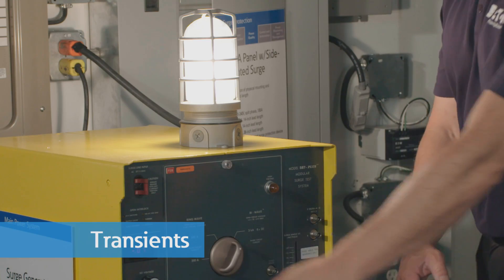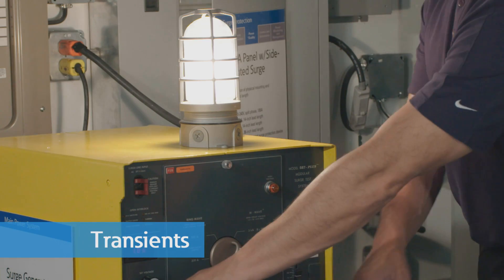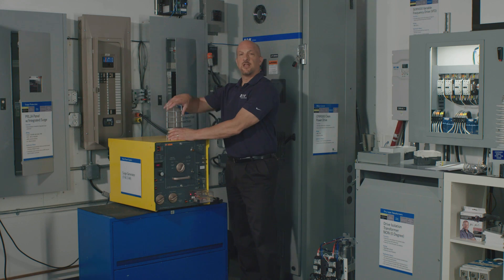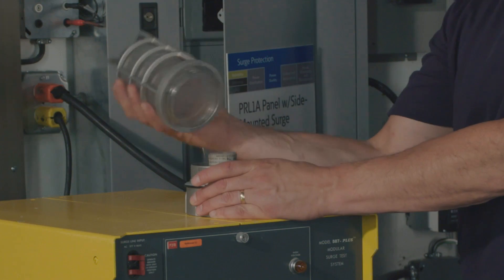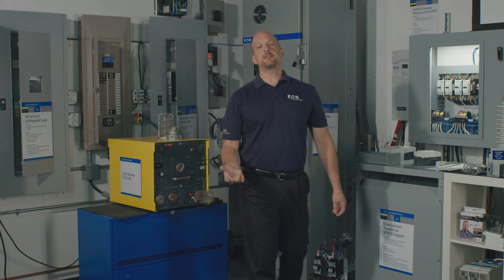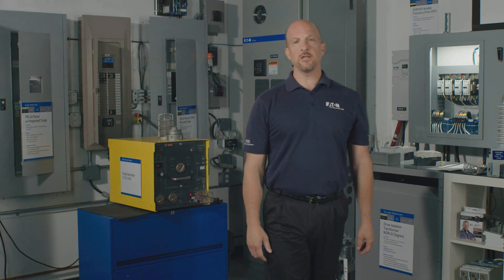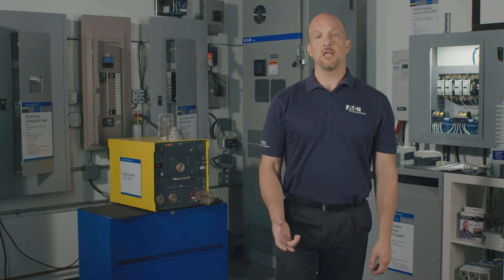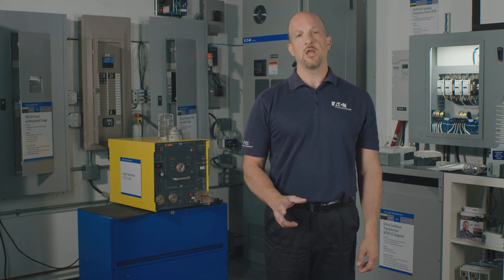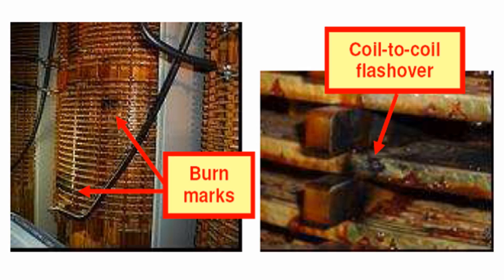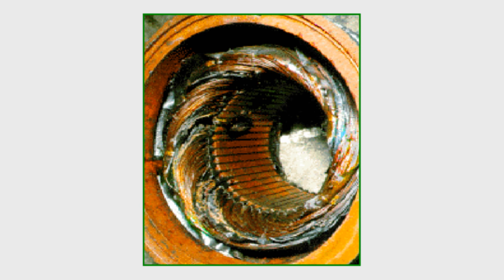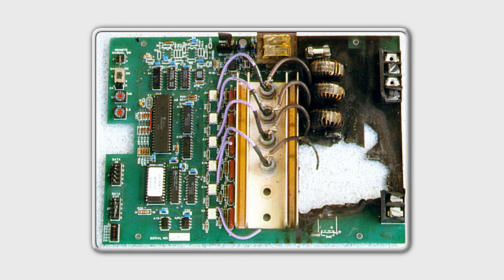Transients or surges are short-duration, high-voltage, sub-cycle events, and their effects can be significant and damaging. Instead of insulation looking like it was baked from harmonics, it will typically have a simple pinhole in the insulation, usually near the end turn. Transients usually result in damage that's hard to recover from — often the equipment must be replaced.